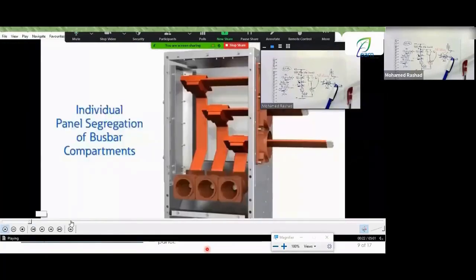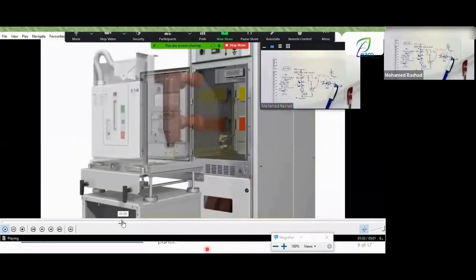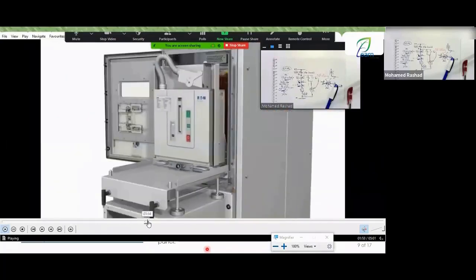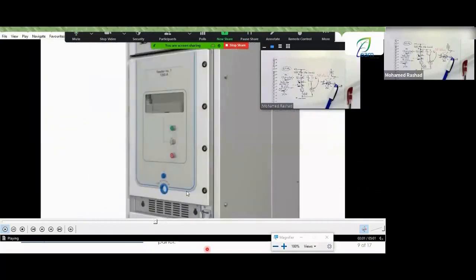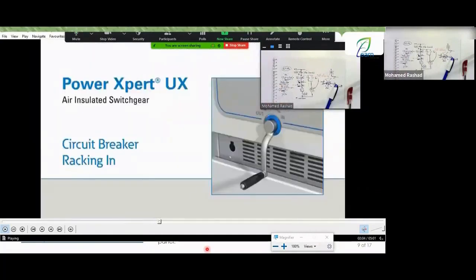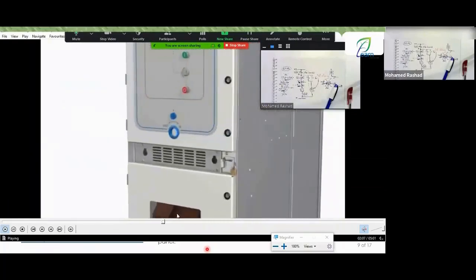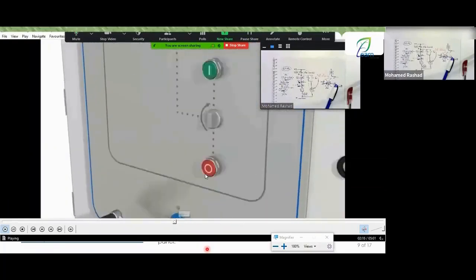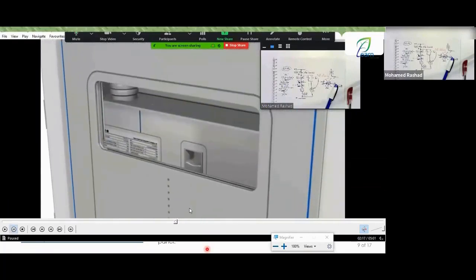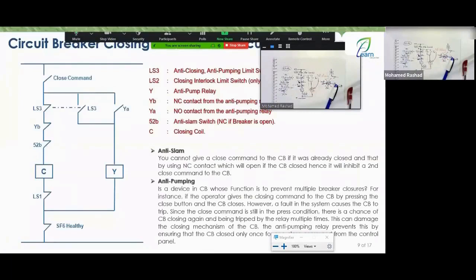Let's slightly shrink this screen a bit. Here you go, this breaker, engineers. Here you have carefully inserted it into the cell, right? Very good. You decided to rack it in, or it was racked in, and you decided to rack it out. So whether you rack it in or rack it out, as soon as you make a slight movement to rack in, or it was racked in and is coming out to rack out, here engineers, now what will happen? What actually happens is that in the circuit breaker, mechanically, you won't be able to close it, meaning you can't close it.